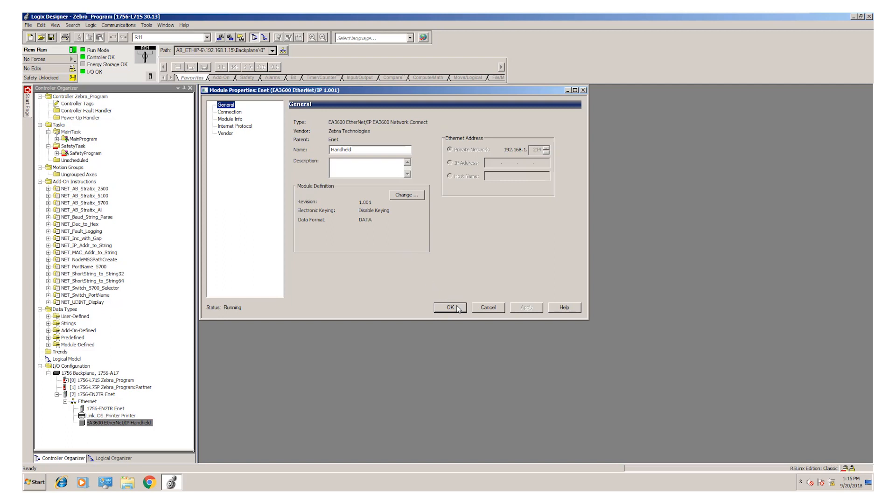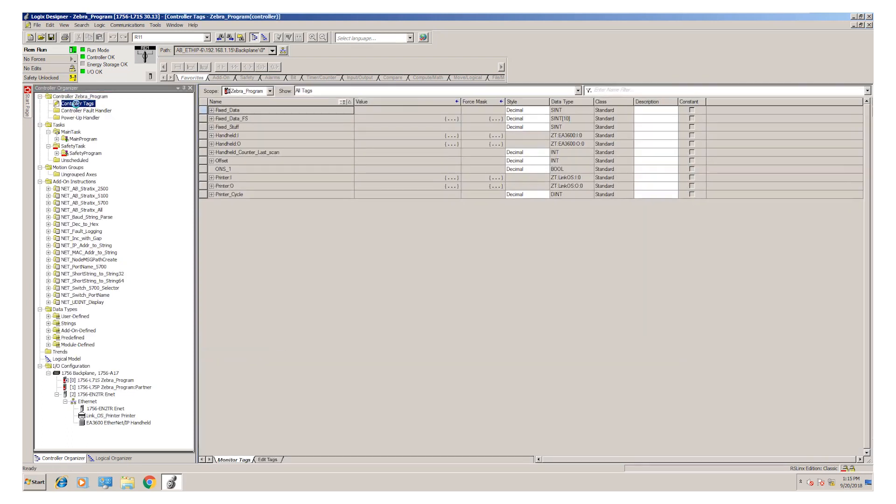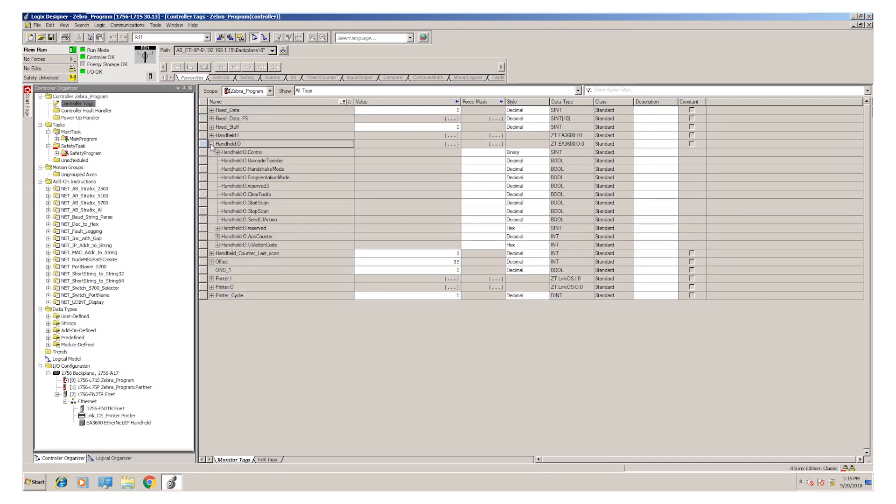Once we create this profile, the controller will establish tags in the tag database. You can see we call the scanner handheld. We have an input array and an output array here. The one bit that we need to be aware of is the barcode transfer bit. This needs to be set to one to get information out of the scanner.